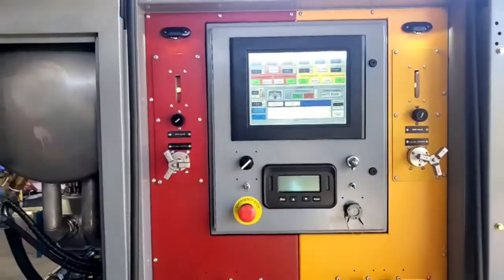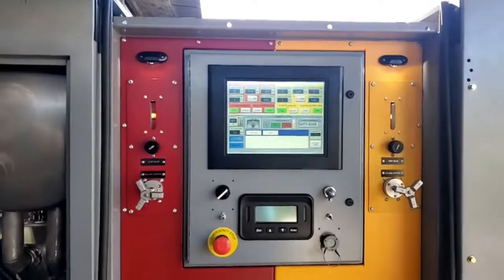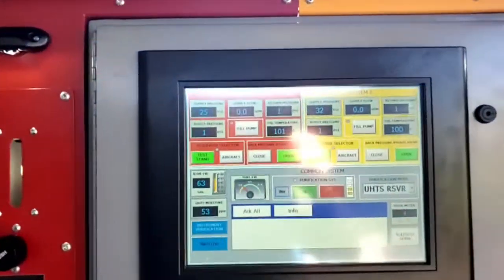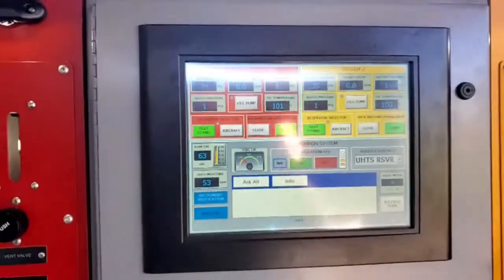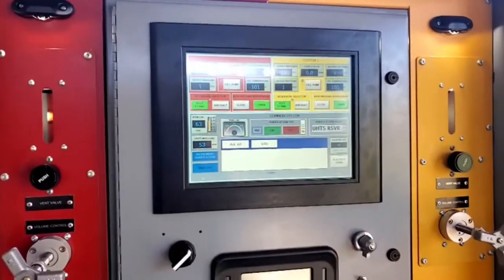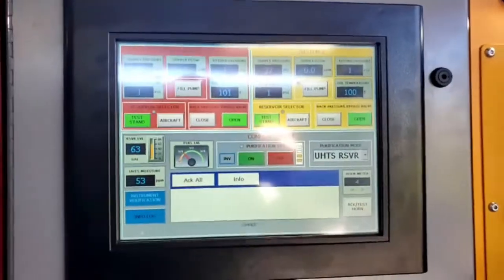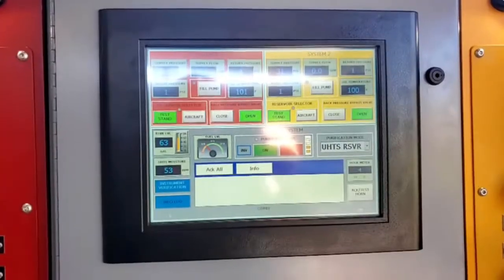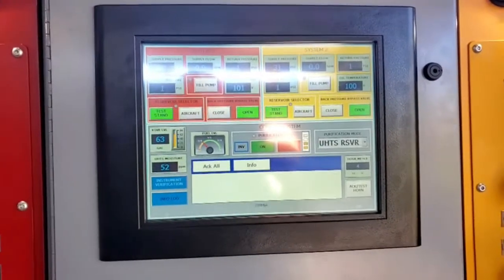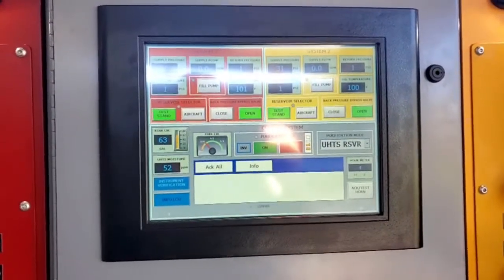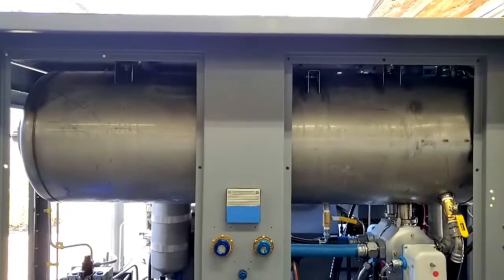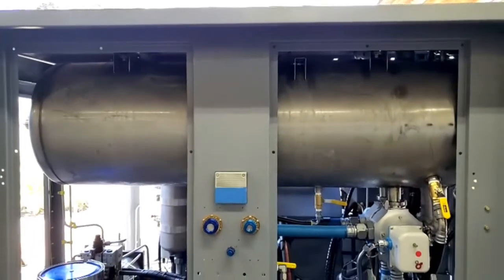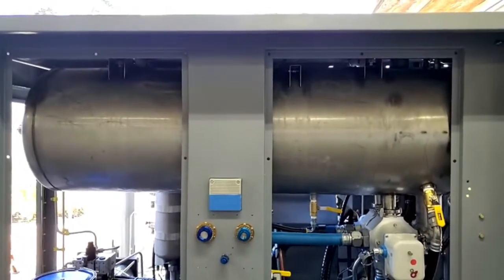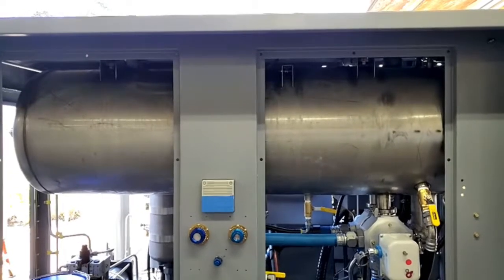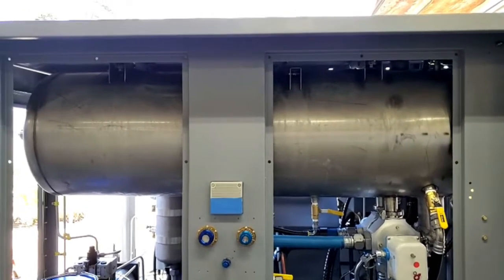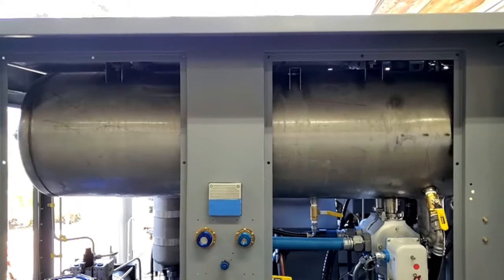As you saw earlier, the reservoir level on the HMI was indicating negative because that unit had been drained and ready for shipment. This unit is fully serviced, and I'm going to walk you through how to service the reservoir so that you can operate the unit. So before we begin, let me give you a little bit of information about this reservoir. It's an 80-gallon size reservoir with about 67 usable gallons inside of it.